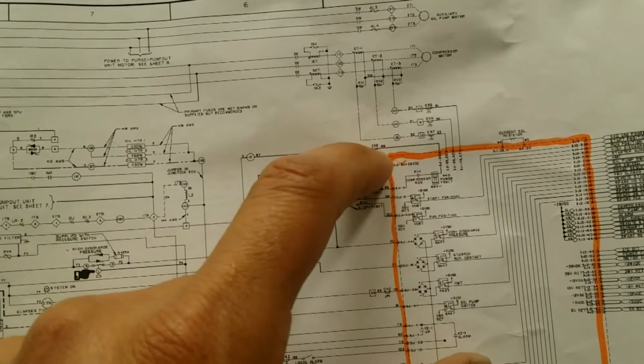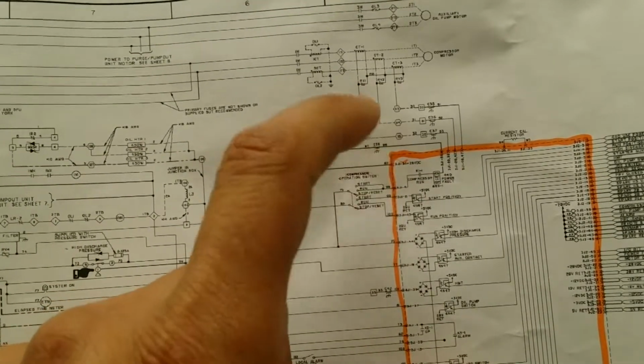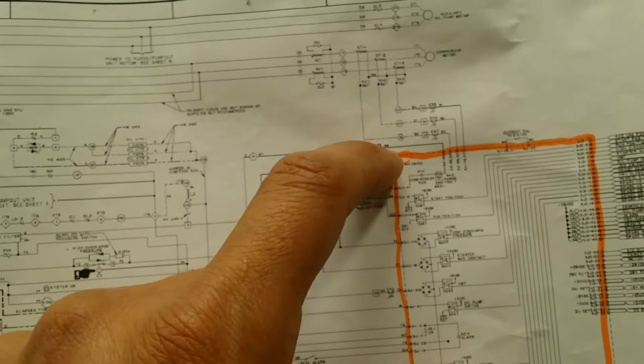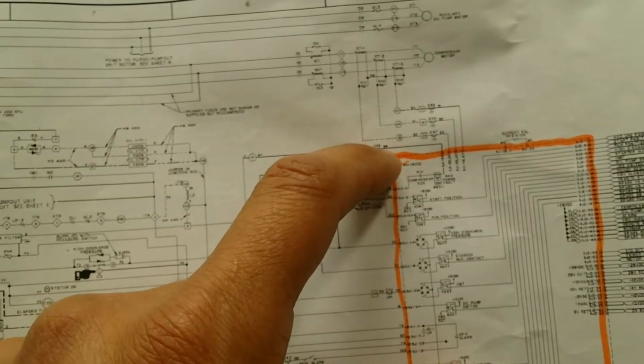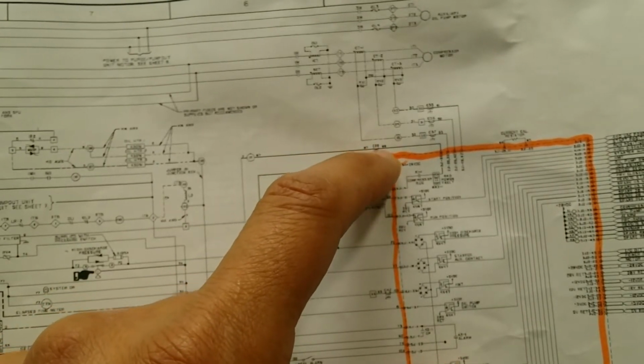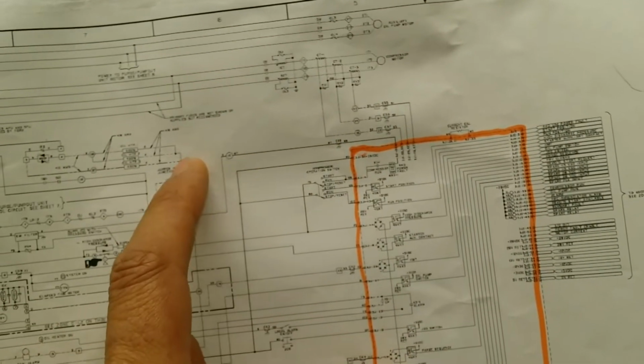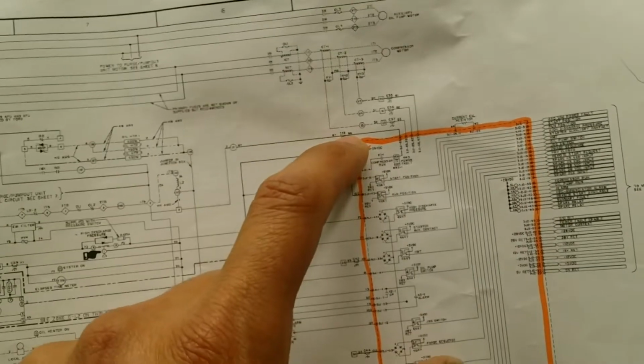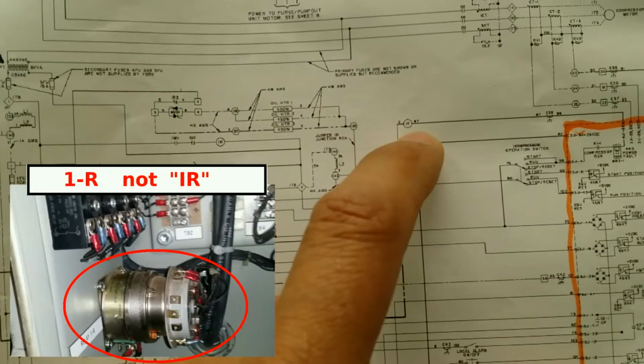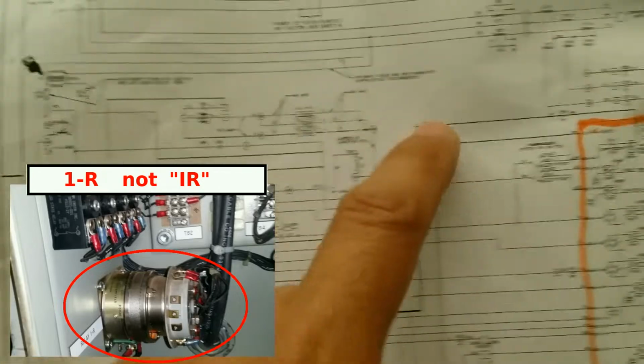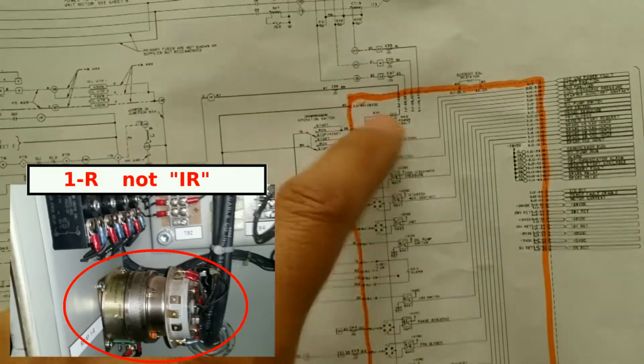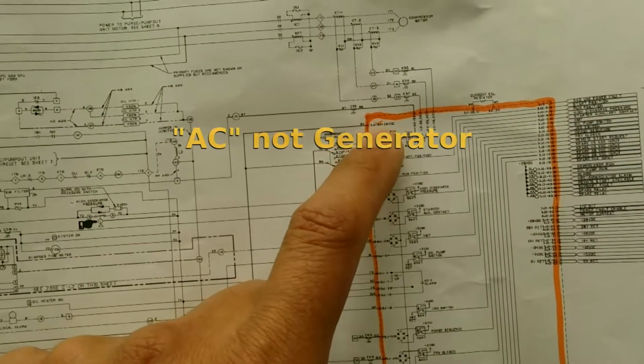Now, the problem with these bleed-through capacitors is that sometimes they ground. I had a problem with this one over here, C58, it grounded out, and what happens is that the AC will randomly start by itself and then shut off by itself. What was happening is that when the ground was over here, it was commanding 1-R to energize. 1-R is how the microprocessor decides to start and stop the AC.